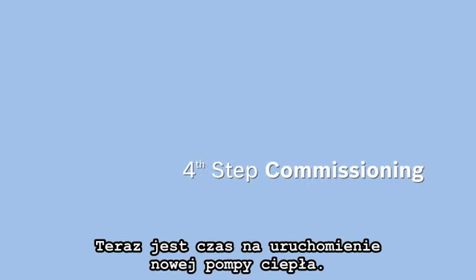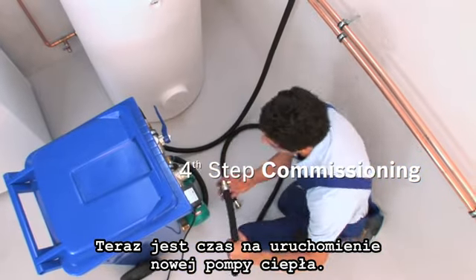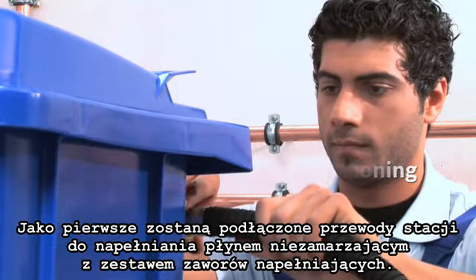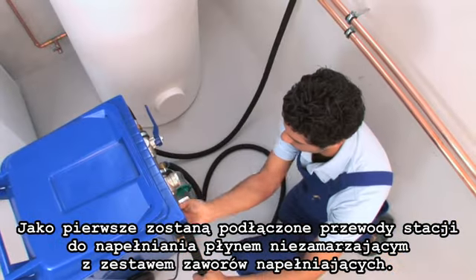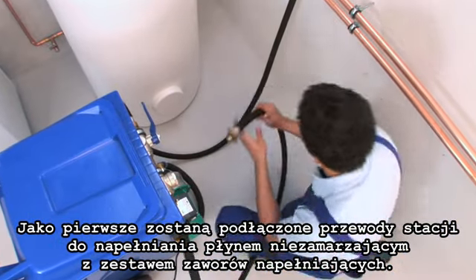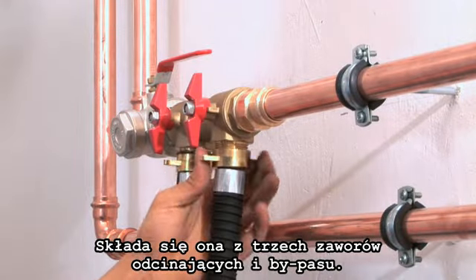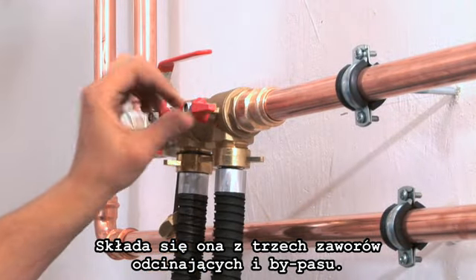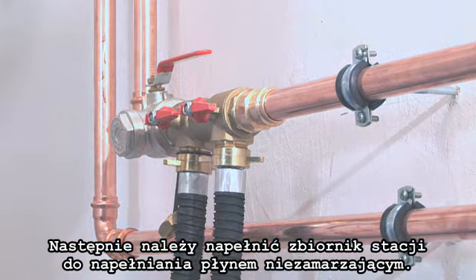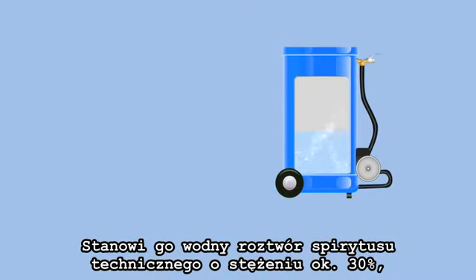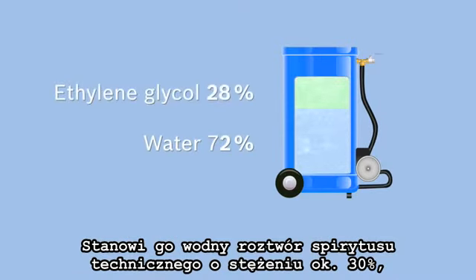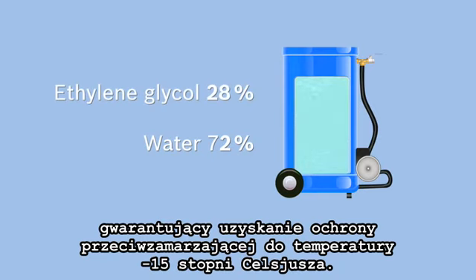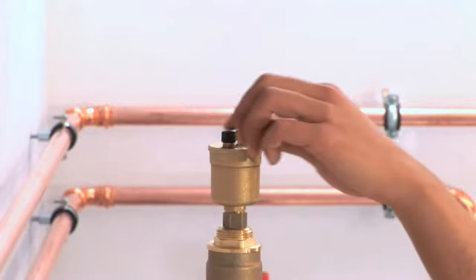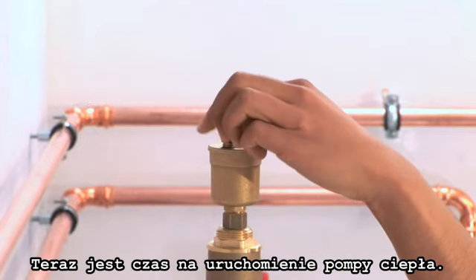Now it is time to start operation of the new heat pump. First of all, the hose pipes of the brine filling station are connected to the filling and rinsing station. It consists of 3 cut-off cocks and a bypass. Then the tank is filled. In the given example, ethylene glycol and water are mixed in order to reach the required antifreeze protection concentration for -15 degrees Celsius. Afterwards, bleed the circuit via the available bleeders.